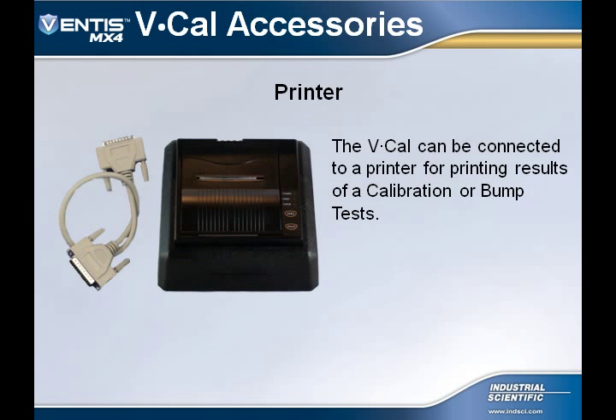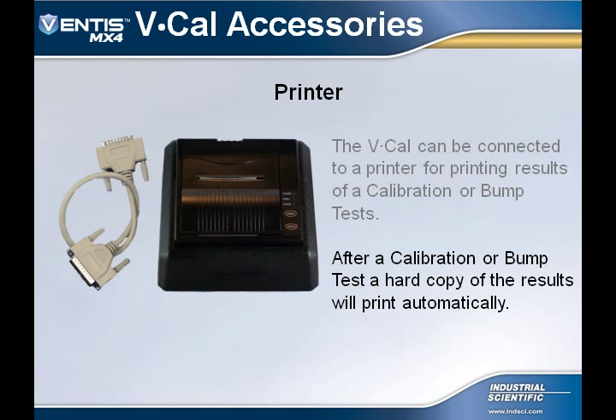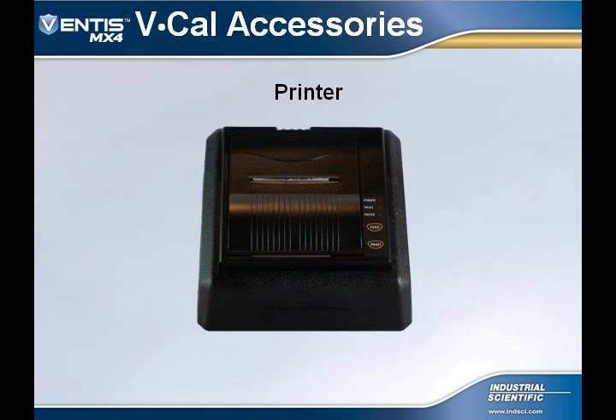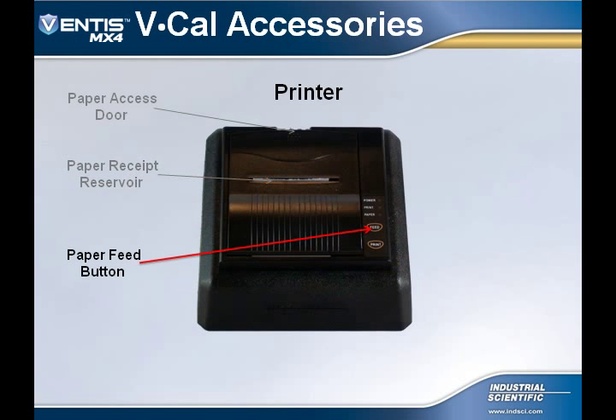The VCal can be connected to a printer for printing the results of a bump test or a calibration. After the calibration or bump test, the printer will automatically print the results. Let's do a brief walk around of the front of the printer. The paper access door for installing or replacing the paper roll. The paper receipt reservoir where the printed results will appear. The paper feed button is to feed the paper into the printer or to provide a line feed.